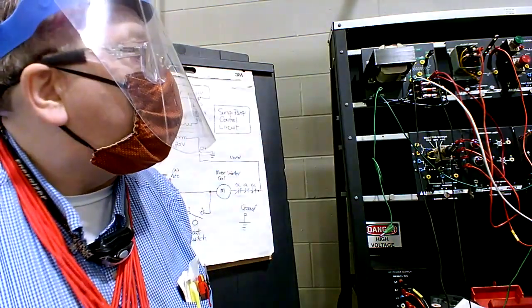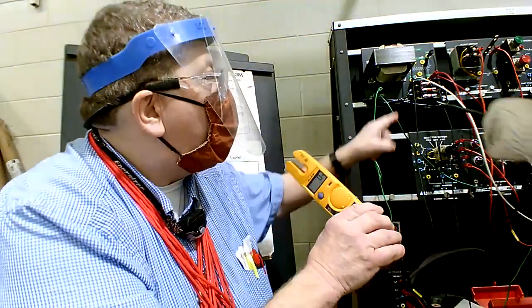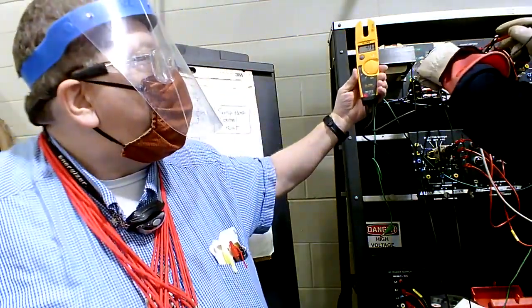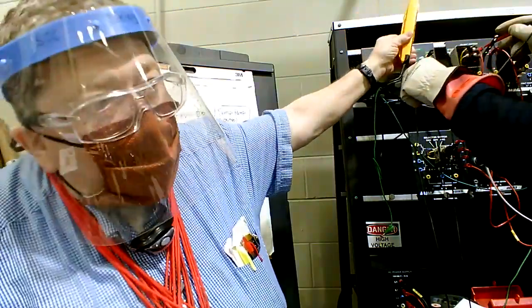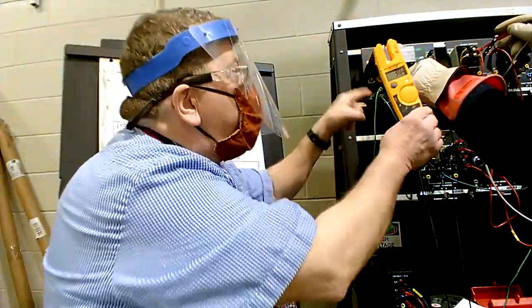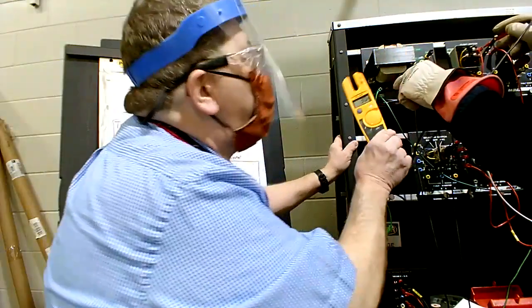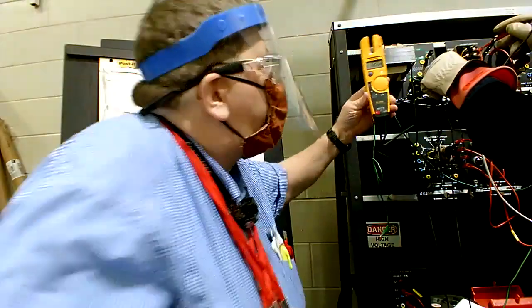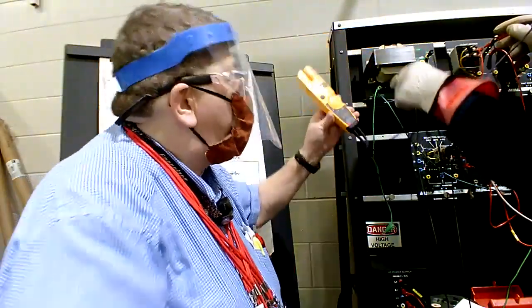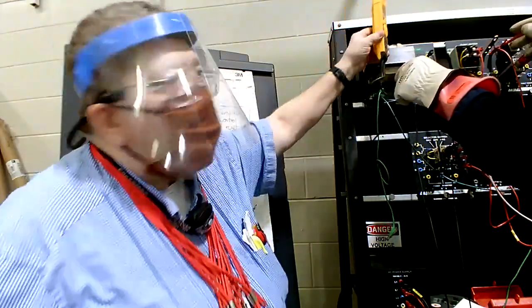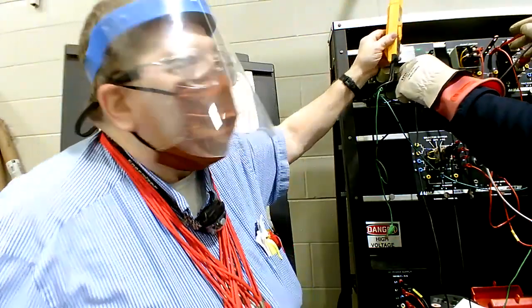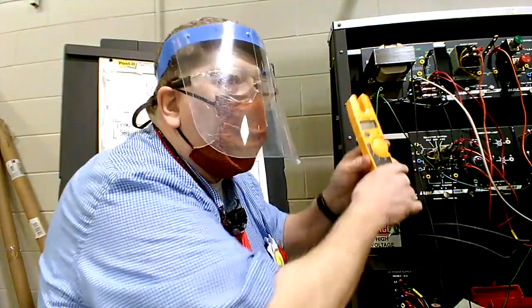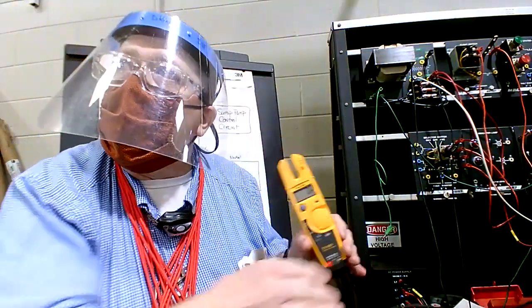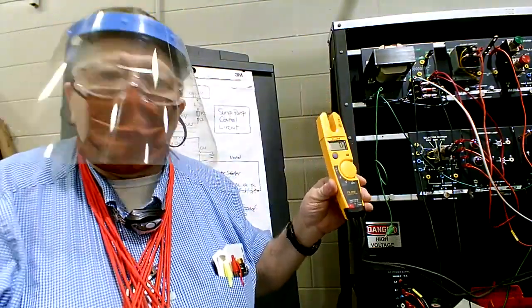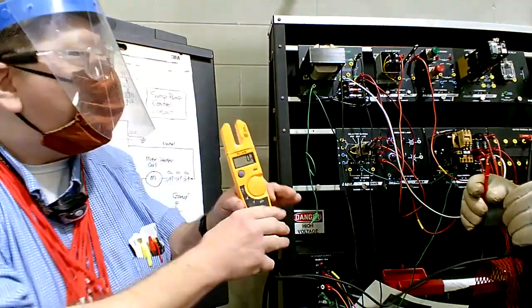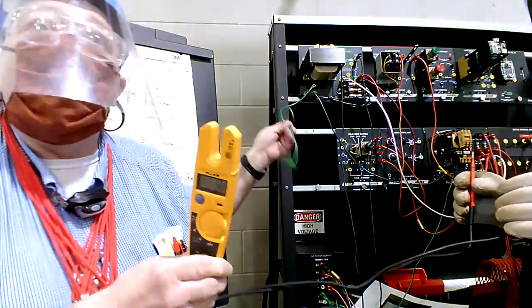Cut your float on. It's still running, isn't it? You still have 120 volts going from neutral to your float. Everybody see it? Now listen, when he checks from neutral to the float, you get 120 volts. Now move over to ground. You're getting 30 volts. You see that? You're reading 30 volts from ground to the float when you don't ground the neutral. You're getting a false reading if you use ground as a reference point for the meter.